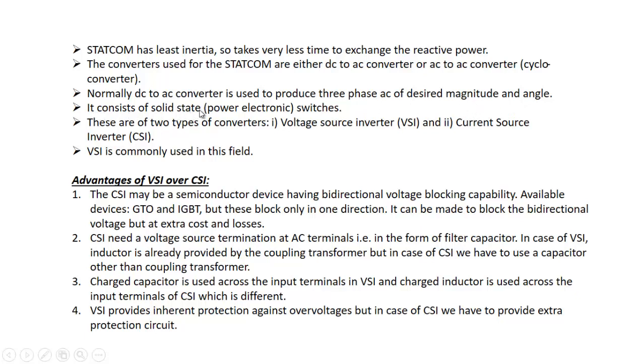STATCOM consists of solid-state power electronics. Voltage source inverter (VSI) is used rather than current source inverter (CSI), because of the advantages VSI has over CSI. The CSI may require semiconductor devices with bi-directional voltage blocking capability. Available switching devices such as GTO and IGBT block only in one direction; making them bi-directional adds extra cost and extra losses, so CSI may not be preferred.